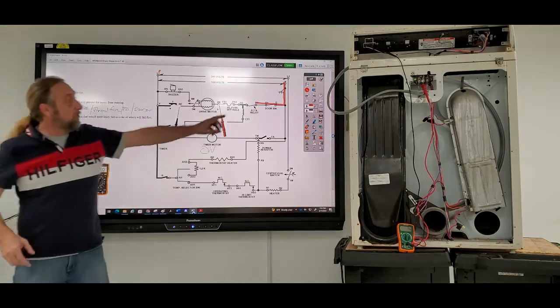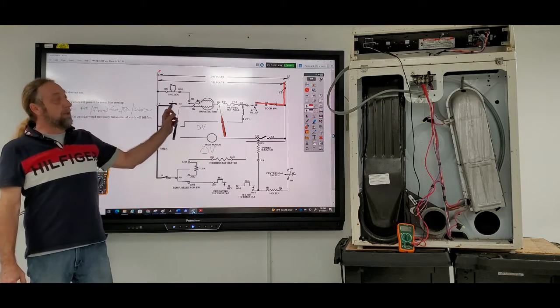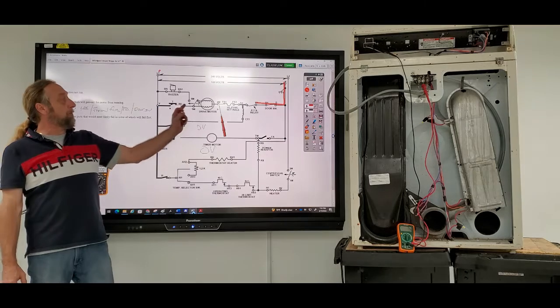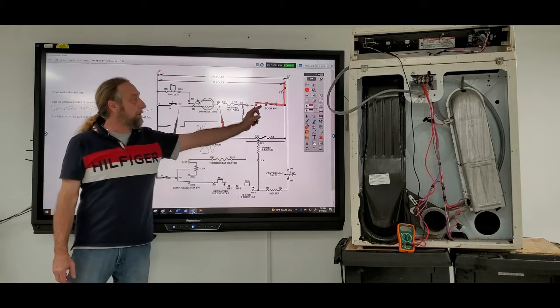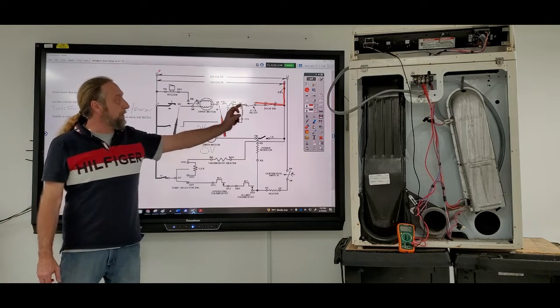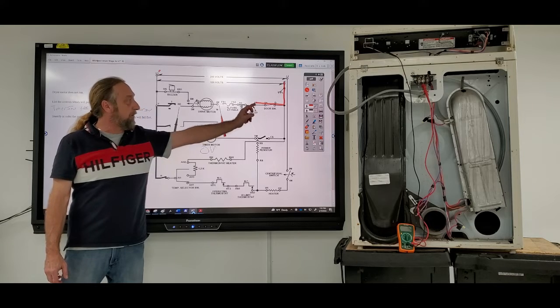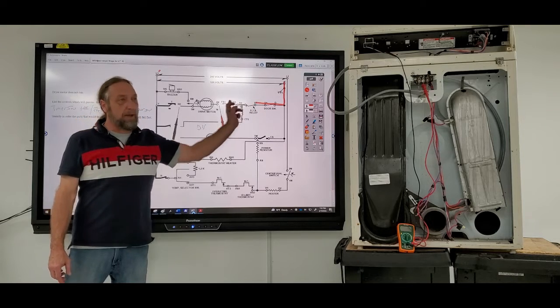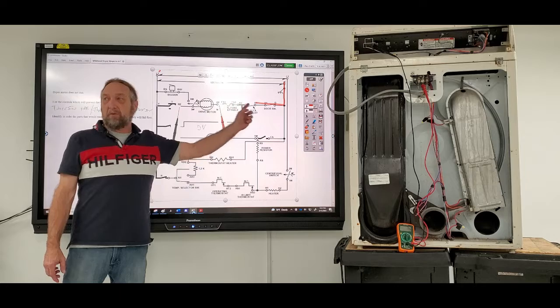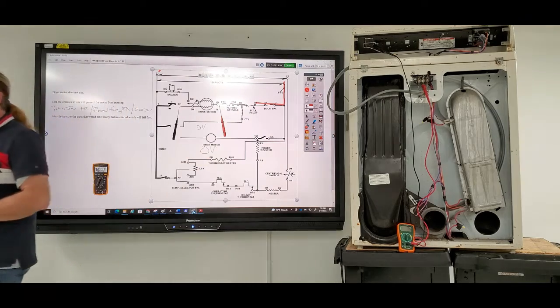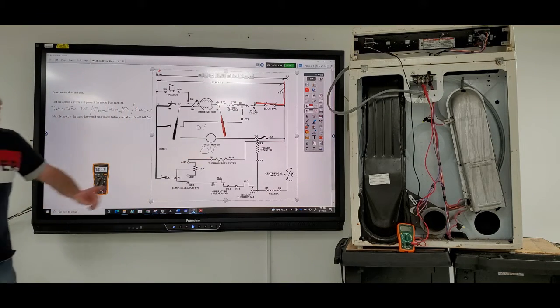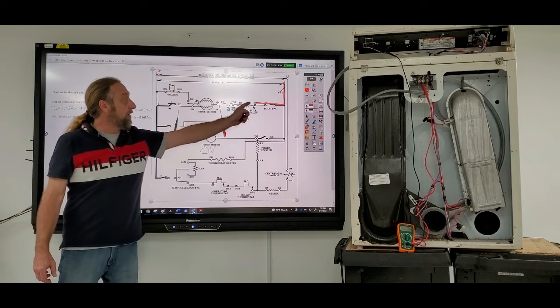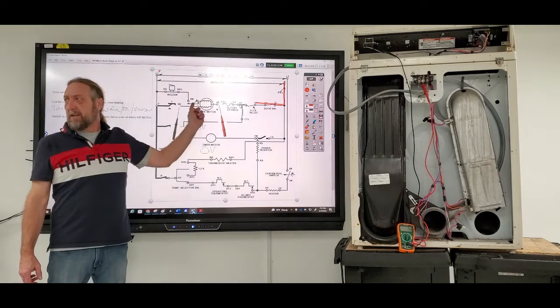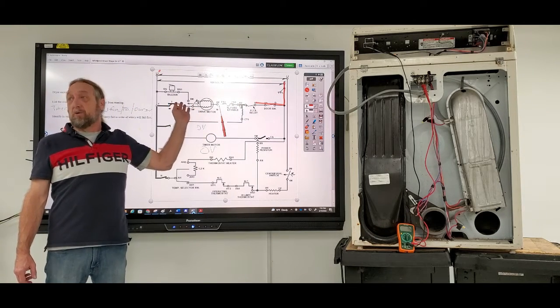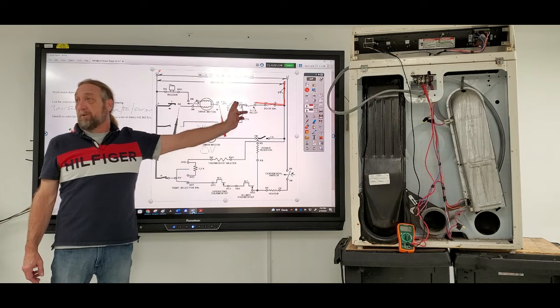Now if this door switch is bad, the voltage tester, the little thing that beeps and lights up, goes beep beep beep... and it stops right there. So I know I have voltage on this side. It's going to pass through the motor and stop at that point, because neutral's here but voltage is here. You say, yeah, but the motor's there—if the motor's not running, the voltage will go up to this point and stop.